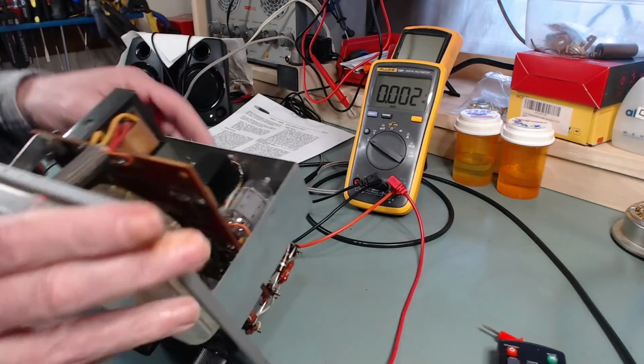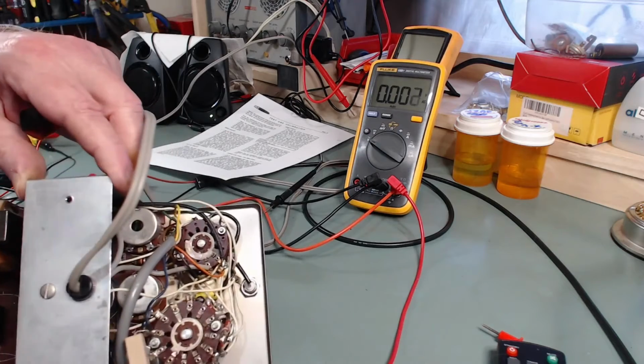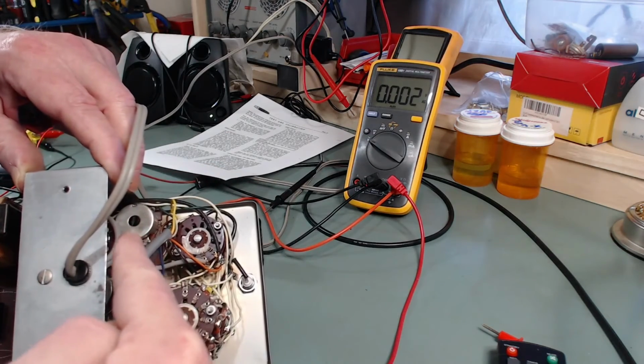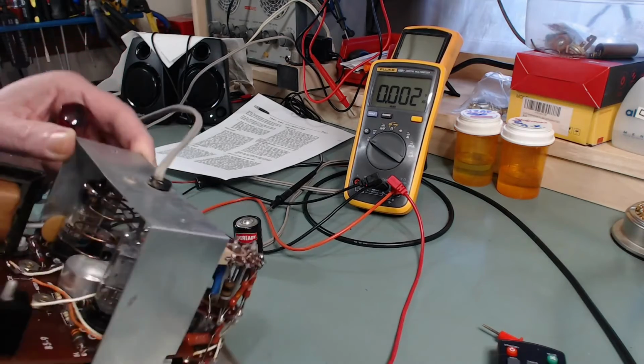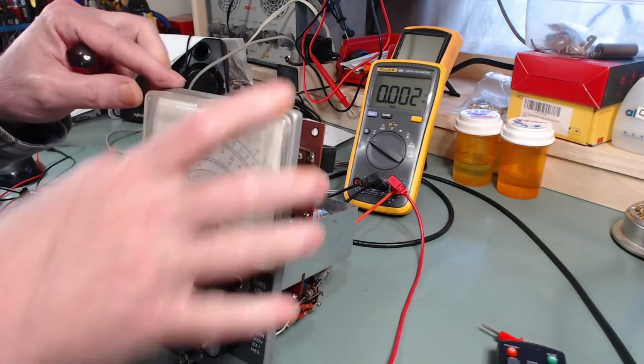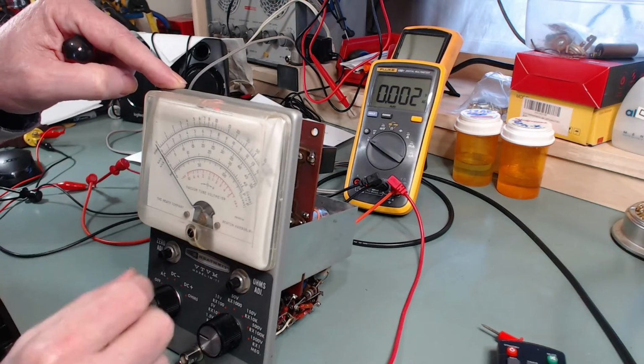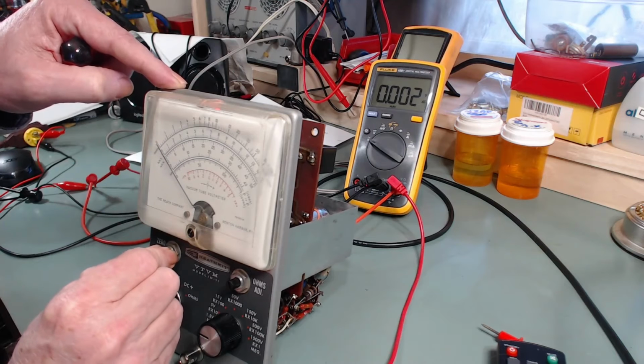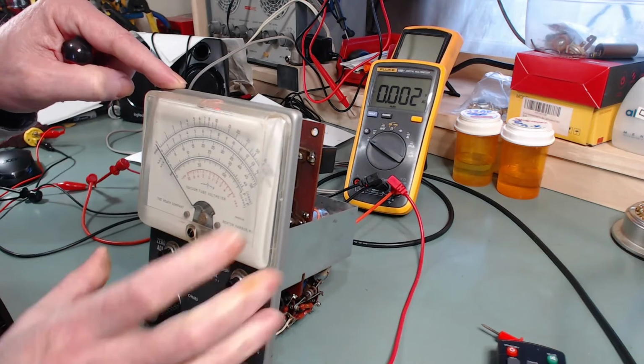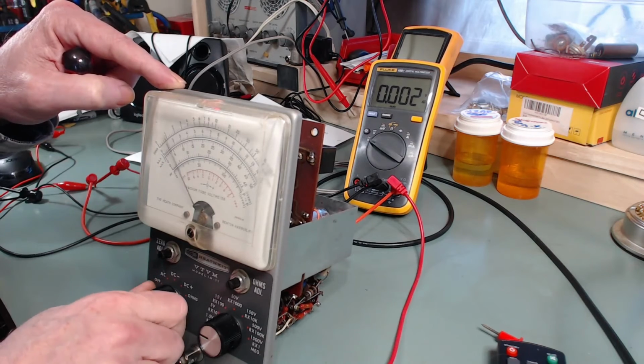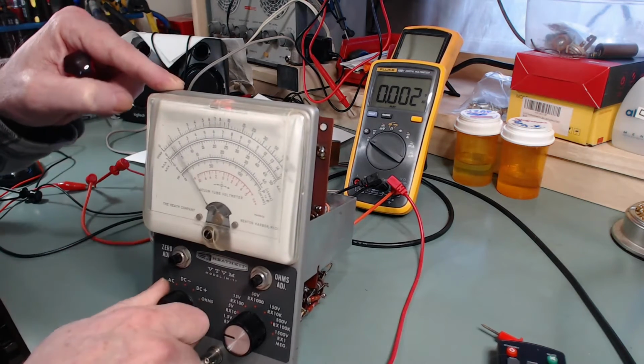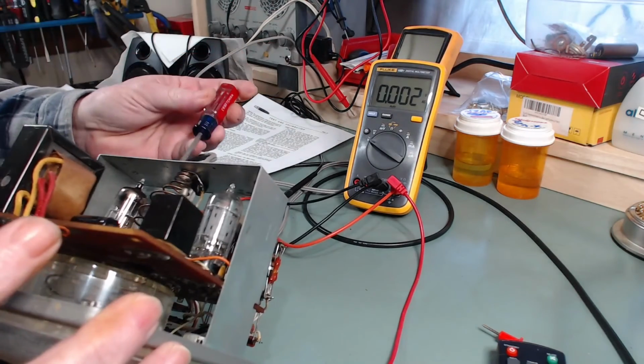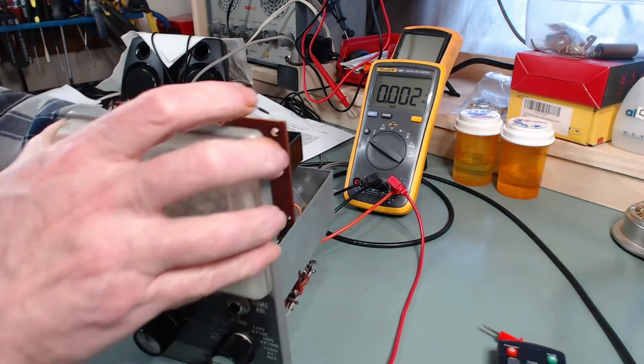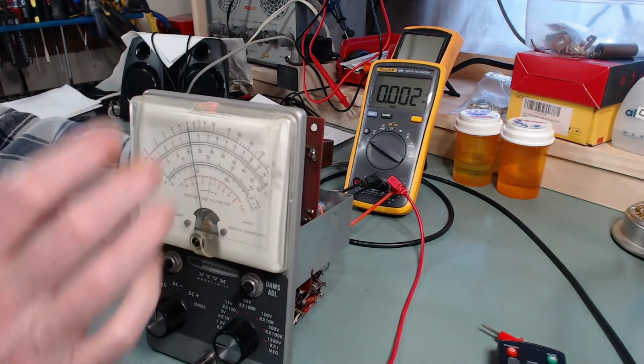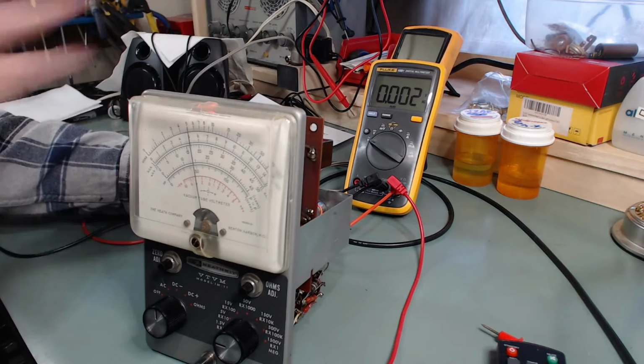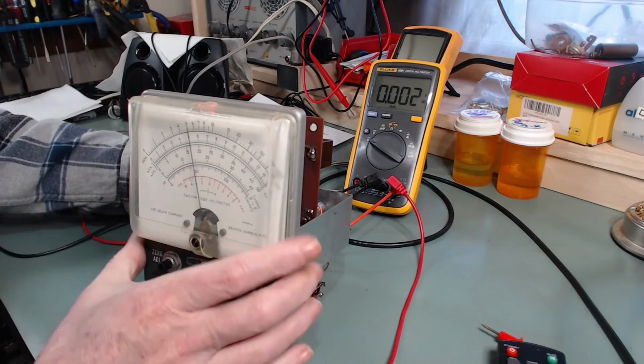The AC cal is this pot right there in the back. And that's the one I'm going to be turning. So the first thing you want to do is, I'm looking straight on. Okay, so I'm going to zero this out, which was actually pretty close. And switch between AC and DC. See how wide that swings. So come back here and be very, very careful. If you're following along, please be very careful, and you're also doing so at your own risk. There's a lot of high voltage back here, line voltage, so please be careful.